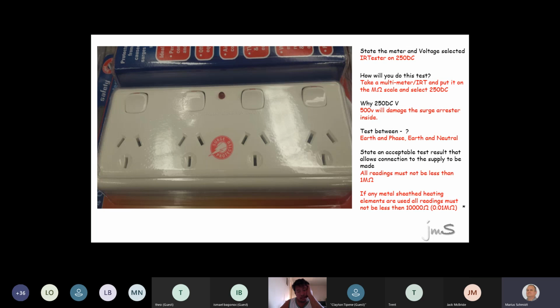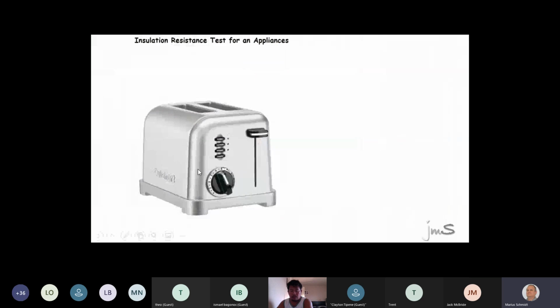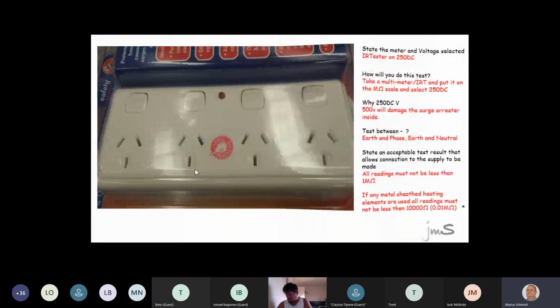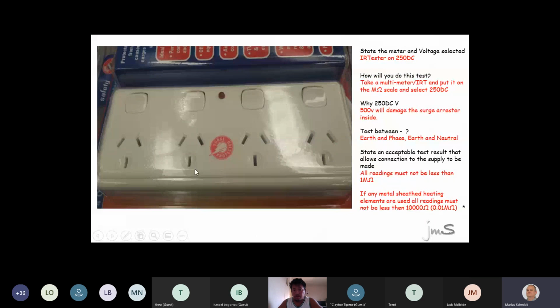Now, guys, this is written in the 3000 book. When you open the 3000 book, it does state 250 volts for any MOVs, metal oxide varistors. A metal oxide varistor is a type of device. As soon as the voltage goes above a certain predetermined value, it will short out and it will blow. So that LED, when it starts glowing and it goes dead, it's over with that.